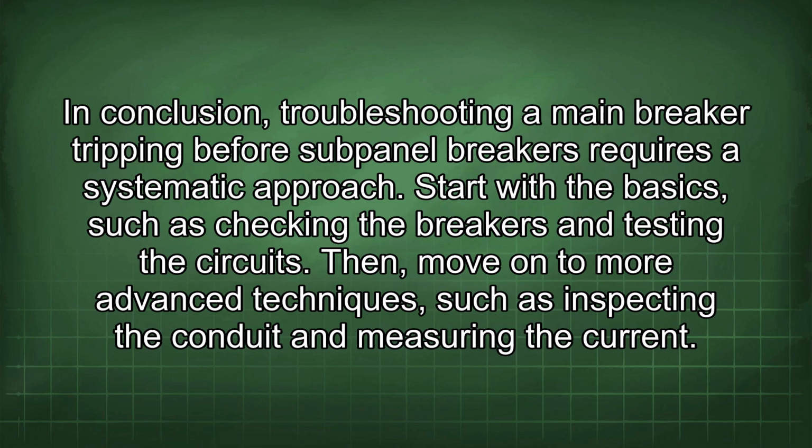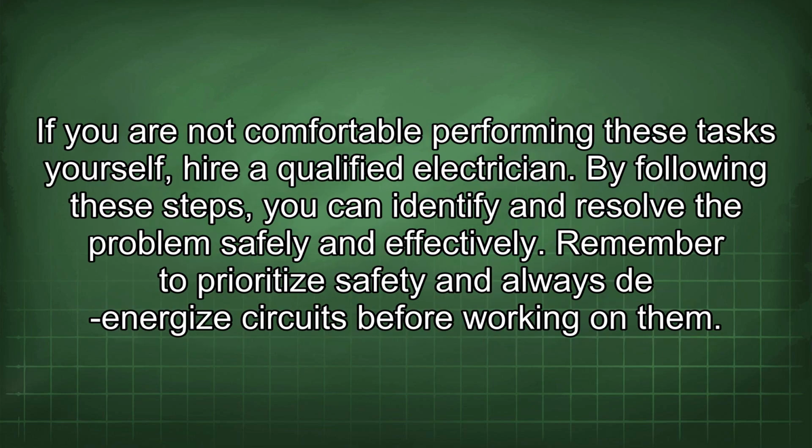In conclusion, troubleshooting a main breaker tripping before subpanel breakers requires a systematic approach. Start with the basics, such as checking the breakers and testing the circuits. Then, move on to more advanced techniques, such as inspecting the conduit and measuring the current. If you are not comfortable performing these tasks yourself, hire a qualified electrician. By following these steps, you can identify and resolve the problem safely and effectively. Remember to prioritize safety and always de-energize circuits before working on them.